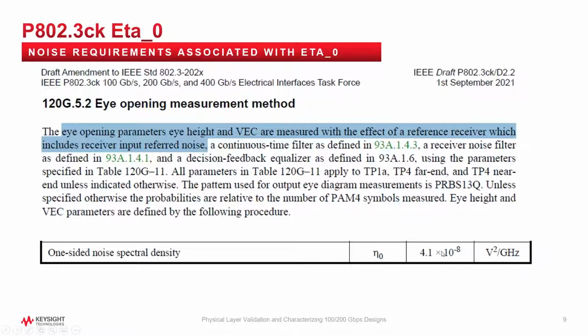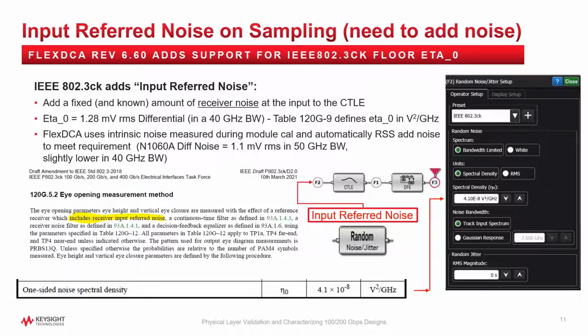And it's set here to 4.1 e to the minus 8 volt squared per gigahertz. And if you evaluate that over a 40 gigahertz Bessel-Thompson response, which is what you normally would do, that translates to about 1.2 millivolts RMS, which means that if you are doing this correctly and you feed a flat line into your instrument, it should measure 1.2 millivolts RMS. And the Keysight tools have been modified to enable you to control this one-sided spectral density through the injection of synthesized noise. In the case of our DCA, our sampling architecture operates well below this noise floor and has to add noise in order to reach the requirements of the reference equalizer, reference receiver. So you see the random noise being injected here. You can turn it off if you like, or you can increase it if you want to do margin tests.